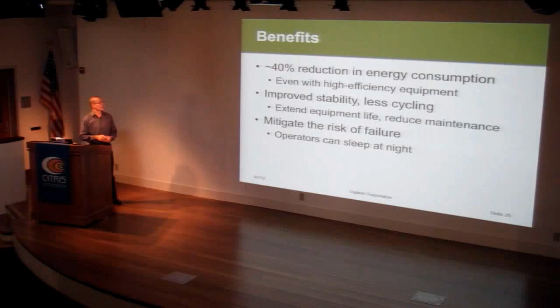When equipment manufacturers design the cooling equipment, they design it to be optimal in a test room. They set it up to simulate a hot summer day, and they run it and see what the COP is, and they say, oh, look at that, that's twice as good as anybody else's, so it's a super efficient system. But if it's out there thrashing around, sometimes surging, and all those things that I just showed you, that can completely erode the efficiency that you get from that. And so that system effect can allow us to get a 40% savings. We can get improved stability from less cycling, less on-off cycling, less up and down. That extends equipment life, reduces maintenance, and makes the operation and maintenance guy's job a lot easier.